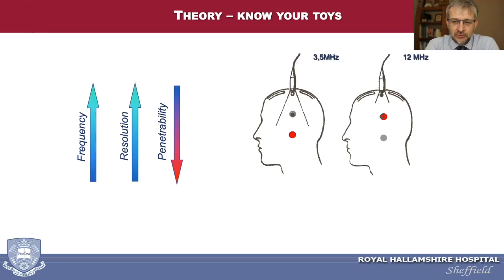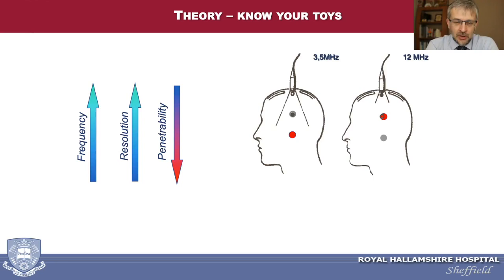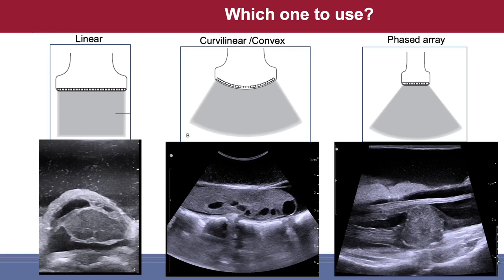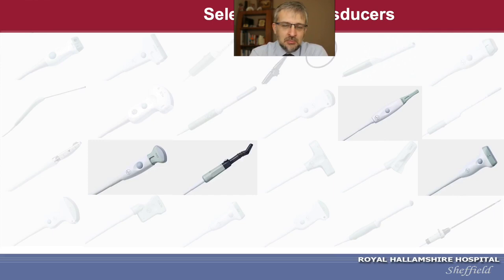An important relationship to remember is between transducer frequency and image quality versus depth. A high-frequency probe gives very good image quality but cannot see deep into the brain — it is useful mainly near the surface. A low-frequency probe can explore the whole head cavity but with lower image quality. My advice: explore and find the probe best for the specific case. Ideally you want a couple of probes you can change depending on needs.